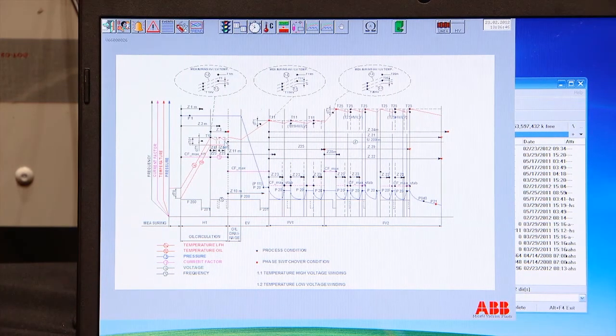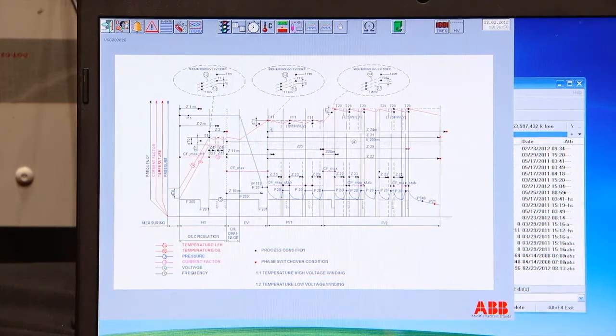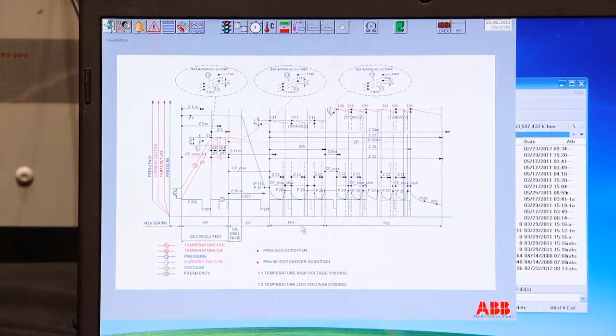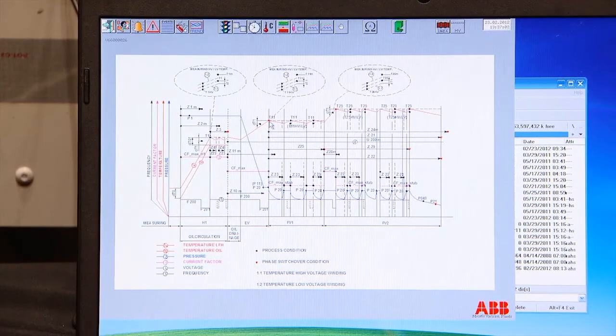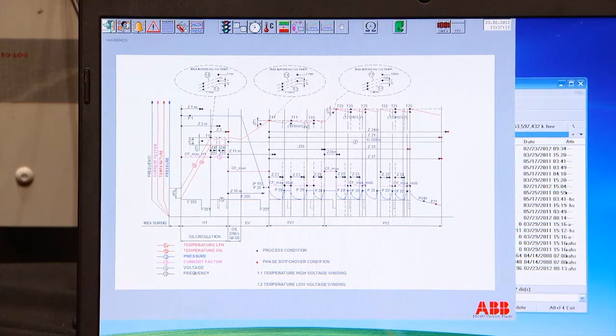Stop for half an hour and heat up again. And after 4 hours, we are at this point. It will go into the evacuation phase, waiting for the pressure to go down, and heat up to our next level. That one is in fine vacuum 1 phase. That's our next temperature set point. So first waiting 4 hours for stabilization, evacuation, heating up in fine vacuum phase.